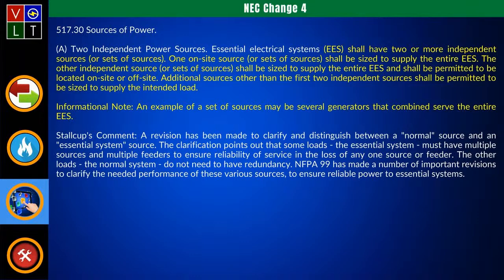Then, dealing with two independent power sources, basically your essential electrical system, they made a revision to clarify and distinguish between what's considered a normal source and an essential system source. Some loads are for the essential system, with multiple sources and multiple feeders, to ensure reliability of service and the loss of any one source or feeder. The other loads, a normal system, don't have redundancy.